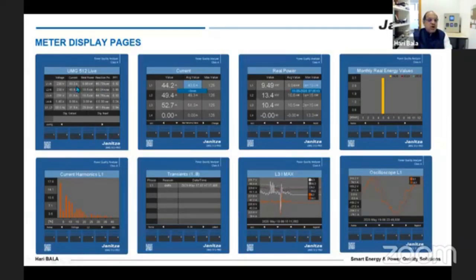You have voltage, current, all in summary page, and current for a particular parameter. You can have real power. You can have monthly energy values for 3 years on a monthly basis, or a bar graph. Individual harmonics as percentage for voltage and current for all the 3 phases, both absolute and percentage. In essence, generally the harmonics is not told in percentage. It is generally told in absolute values, which is available in our meters. And then we also have the transients, which can be captured, and then the waveforms can be seen, plus also the oscilloscope functionality for all the voltage and current waveforms.